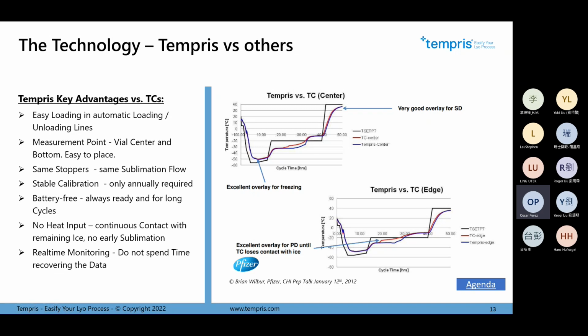First of all, many other technologies are not measuring exactly in the center and the bottom of the vial, where the remaining ice is during sublimation. And this is very important. If you are measuring in the edge of the vial, in a corner, the ice sublimates much earlier because it's directly in contact with the tray. If you don't have this bended part of the vial in the bottom, you will not really have control of the remaining ice.